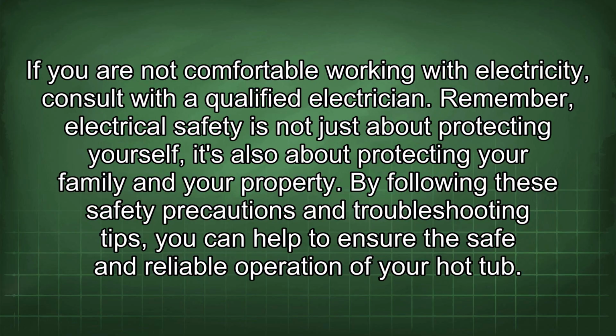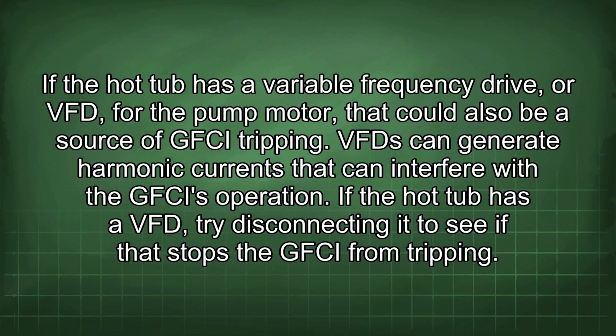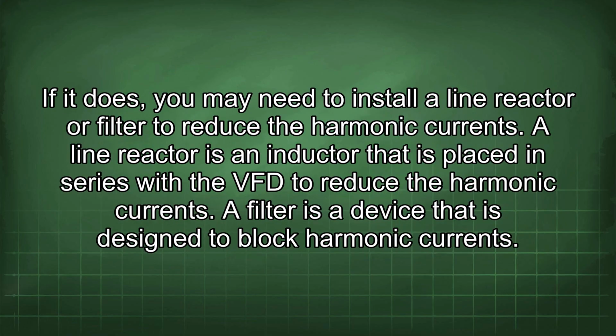By following these safety precautions and troubleshooting tips, you can help to ensure the safe and reliable operation of your hot tub. If the hot tub has a variable frequency drive, or VFD, for the pump motor, that could also be a source of GFCI tripping. VFD can generate harmonic currents that can interfere with the GFCI's operation. If the hot tub has a VFD, try disconnecting it to see if this stops the GFCI from tripping. If it does, you may need to install a line reactor or filter to reduce the harmonic currents.